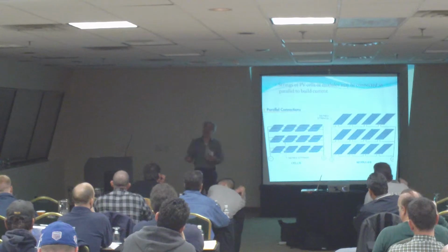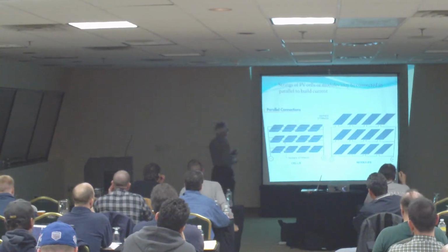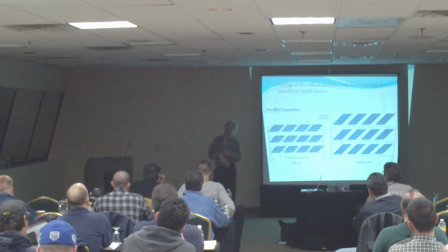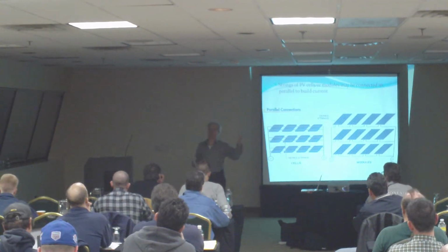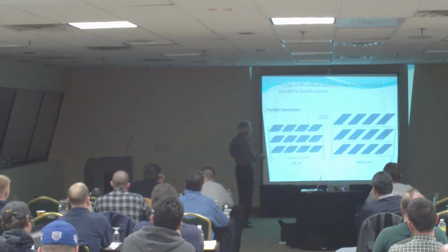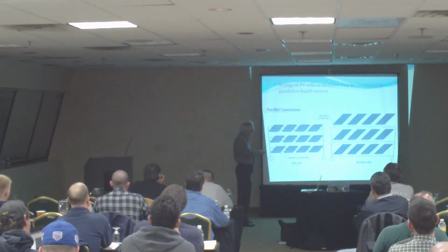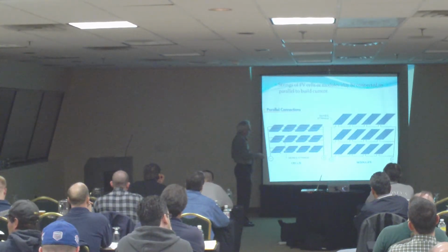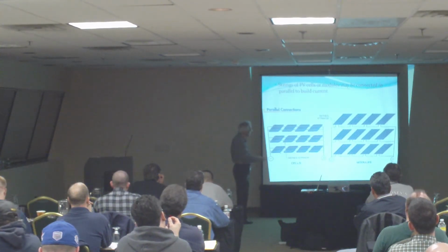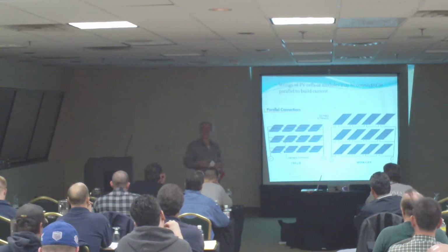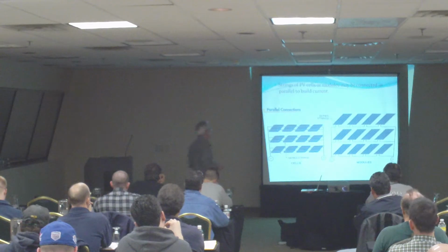So if I go into troubleshooting and I expect this module in here to give me so much current, and something is wrong up there, what do I do? Well, I can do a couple things, right? I can stick my probe, my clamp-on meter, right here. I can measure the current here, I can measure the current here, I can measure the current here and find out whether that string is working.